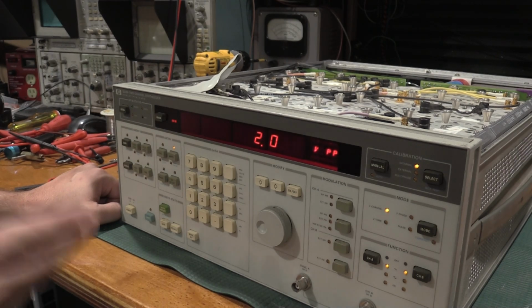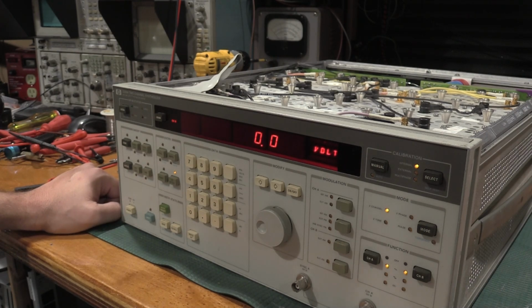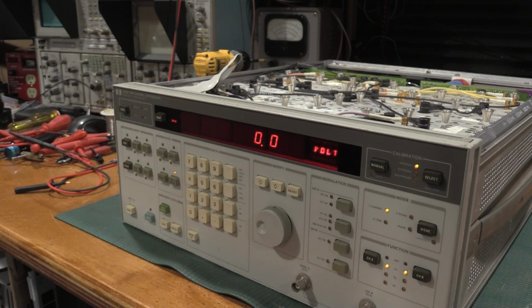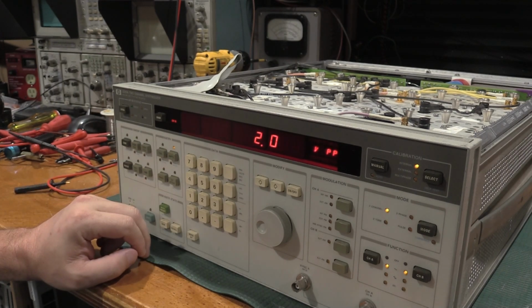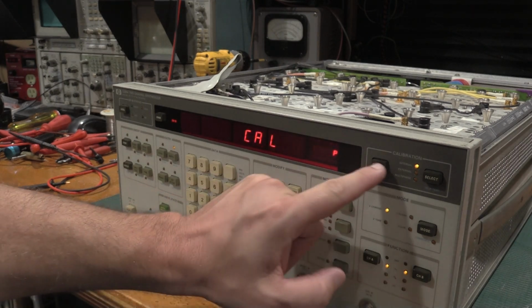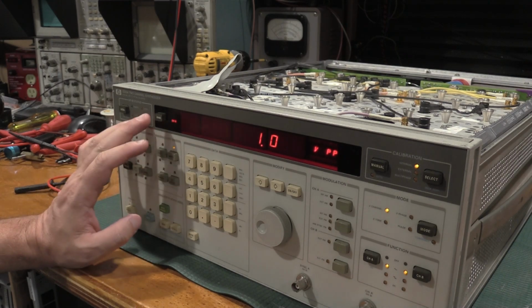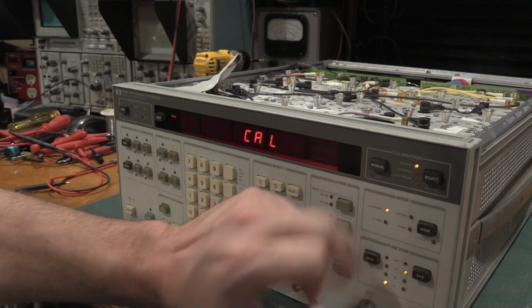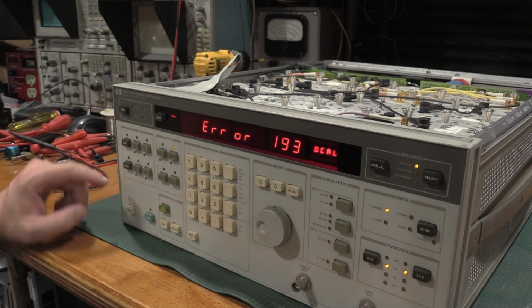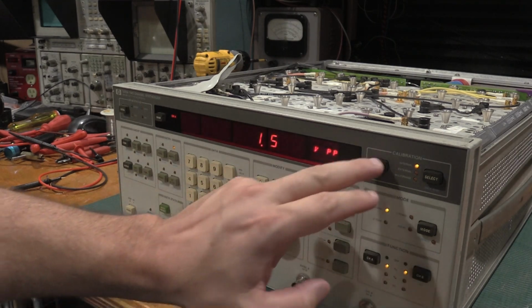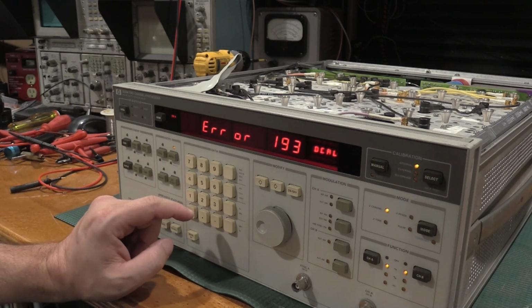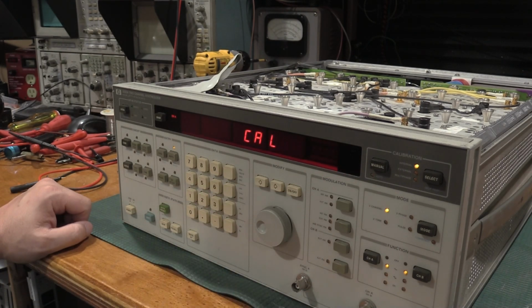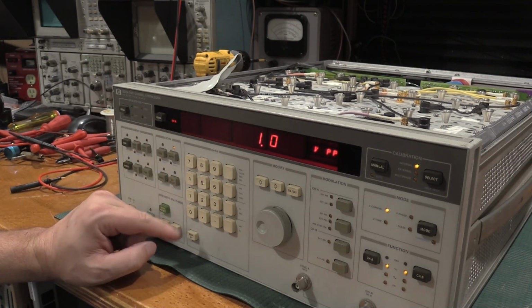Okay, so it is now happy at a 0 volt DC offset. So our K5 relay on the reference board and calibrator board has improved the situation. But this means we have more relays we have to find, because if I drop the amplitude on channel B, it passed then. And on channel A, let's check 1.5 volts - no. 2 volts, which calibrated before - no, which means it's a channel B problem.